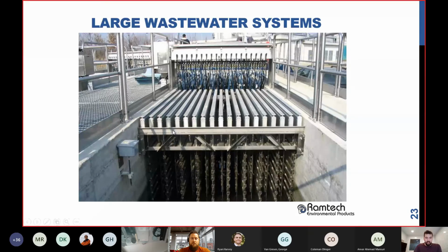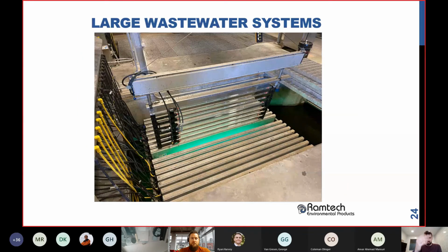This is the support racks here that hold the weight of all these modules, and you can actually walk on these. I'm a very big person, and even I can walk on them. So this is just an example photo of one of those modules pulled out. You can see why the newer generation systems like the Sigma are looking at those angled lamp systems. Now it does make for a deeper channel, but much easier to take care of, and the lamps in that system are much more powerful, so you need considerably less.